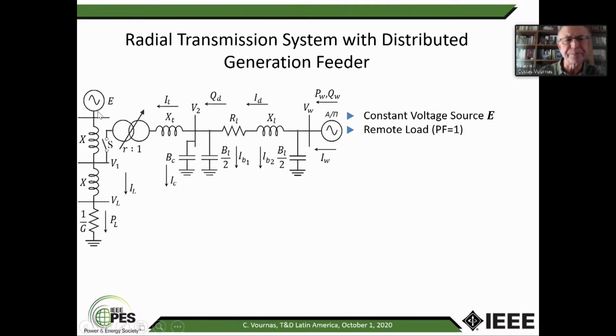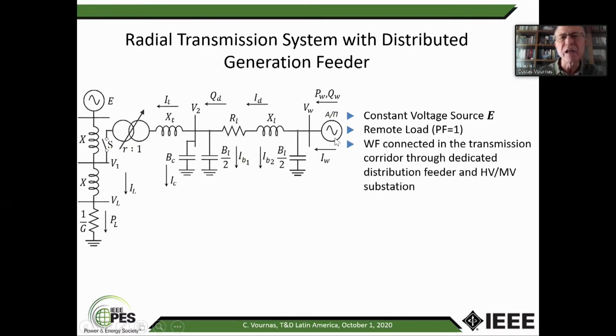You see the transmission corridor is reactive. And in the middle of this corridor, I have connected what I call a dedicated feeder with a wind farm. So you see here the wind farm. By the way, I apologize that some of the writing is in Greek, but I'll explain everything. You don't have to learn Greek to follow this. So this is the wind farm. This is the voltage of the wind farm. This is the feeder, the medium voltage feeder. I have some number of capacitor banks that can control the voltage here, and I have a tap changer on the medium voltage, high voltage transformer connecting the wind farm to the transmission system. This is called the load tap changer, or LTC.